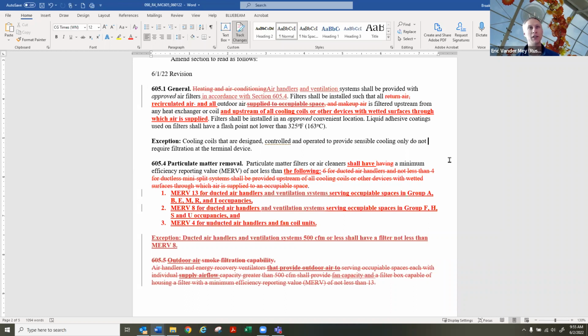I don't know if there's a lot of units. Well, I guess it's possible on a custom air handler or something, but if you have a fixed plate heat exchanger that has no cross contamination potential, do you really need a MERV 13 filter on the exhaust? So we could add an exception too for ventilation system. I don't know. I could come up with some language, I guess. I'll work on it.